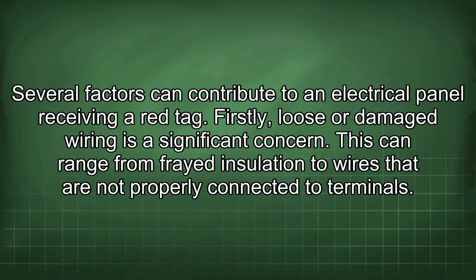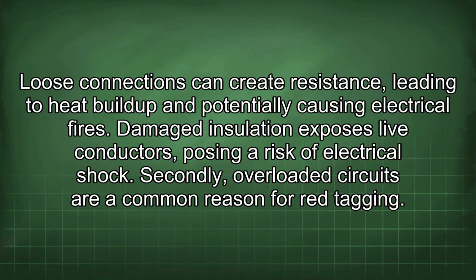Firstly, loose or damaged wiring is a significant concern. This can range from frayed insulation to wires that are not properly connected to terminals. Loose connections can create resistance, leading to heat buildup and potentially causing electrical fires. Damaged insulation exposes live conductors, posing a risk of electrical shock.